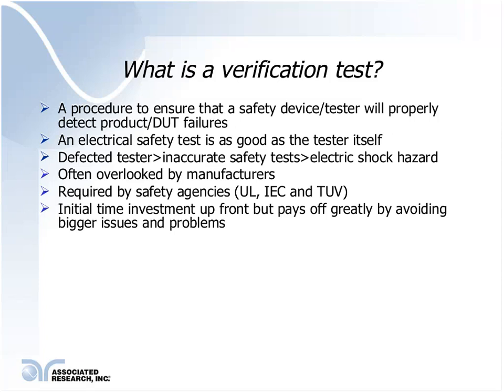Now, while the task of setting up a test verification can seem daunting, it's a simple matter of having the necessary equipment and procedures in place so that the process is easy to follow. We know that an electrical safety test is as good as the tester itself. If the tester is defective, it will lead to inaccurate safety tests, which in turn can lead to bigger issues like electrical shocks and other safety hazards for the user.